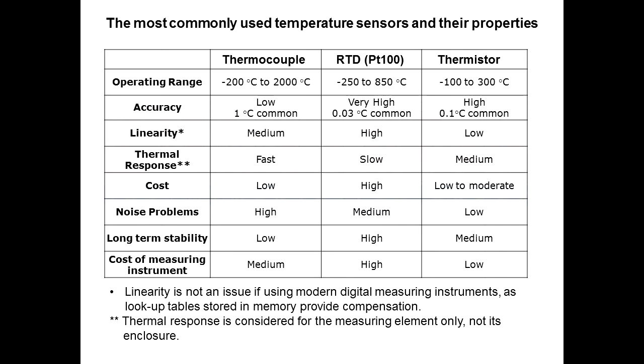Noise problems, you should be shielding your RTDs also. This is very low voltage here. This is medium voltage. This is a high resistance voltage, so you don't have much of a problem with noise issues there. Long-term stability, RTDs are much higher than either thermocouples or thermistors. The cost is highest for RTDs and the meters, but if you need accuracy, that's the best way to go. On a thermocouple, you have to add the accuracy of the meter and probe together. Most of the time, RTDs and thermistors are sold as a system where the two readings are combined together.